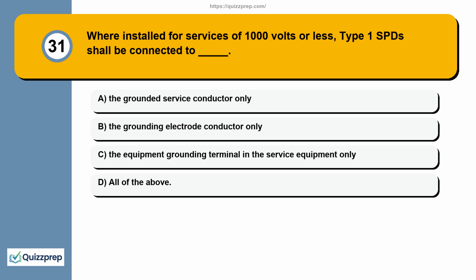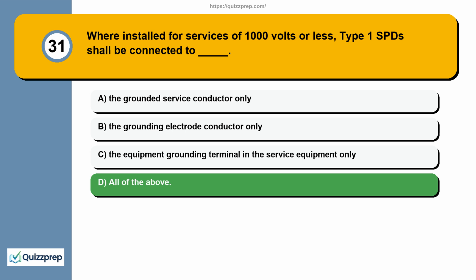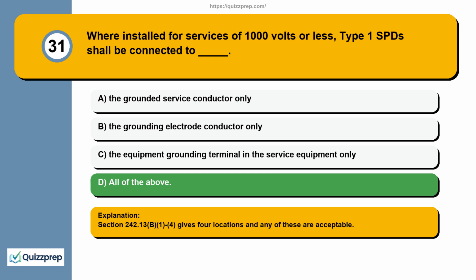Question 31. Where installed for services of 1000 volts or less, Type 1 SPDs shall be connected to the grounded service conductor only, the grounding electrode conductor only, the equipment grounding terminal in the service equipment only, all of the above. Section 242.13(B)(1)-(4) gives 4 locations and any of these are acceptable.